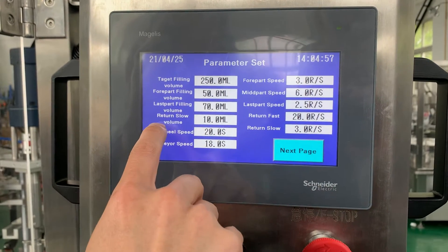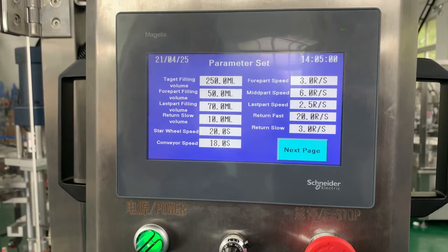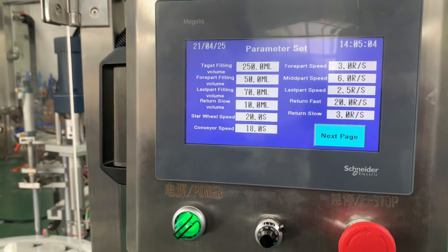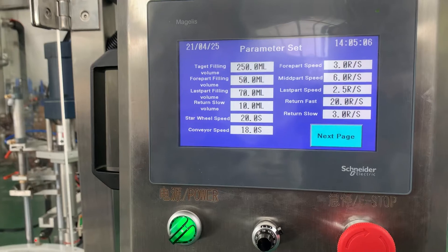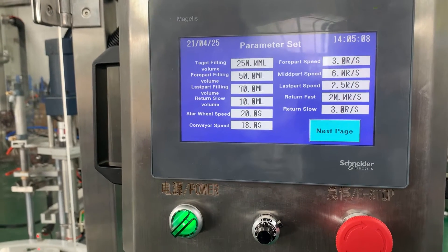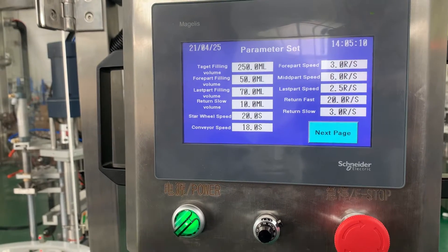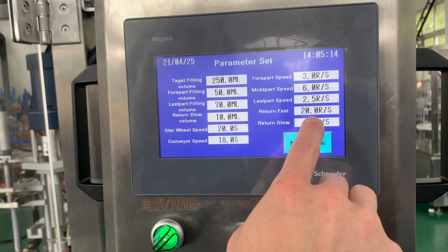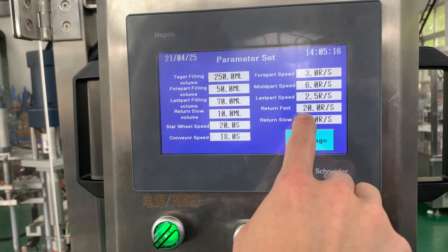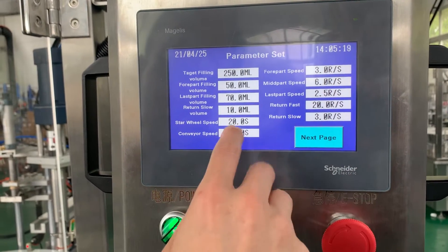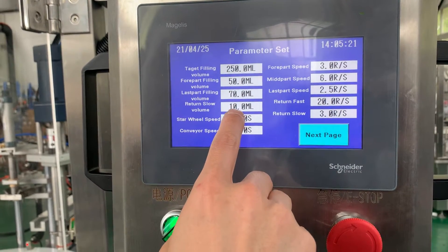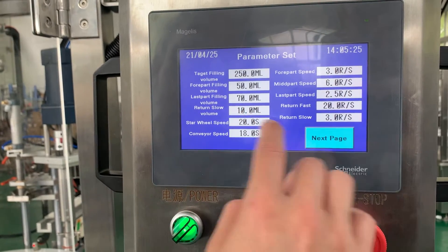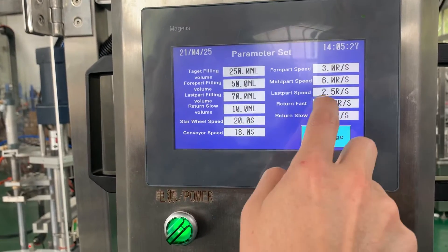The return slow volume is the volume the servo sucks back in after the piston pushes up. The return uses two different speeds: the first part uses high speed at 20 rounds per second, and the last part distance is only about 10 milliliters.